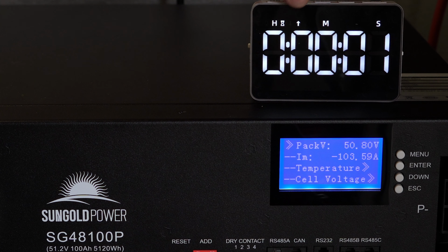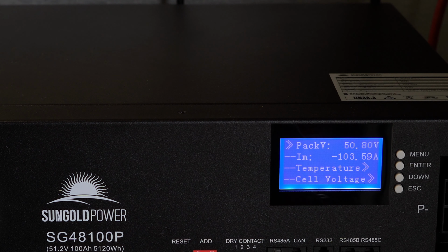All right, clearly running at just a little bit over that rated 100 amps of discharge is not a problem. So we did it for a full 20 minutes. Let me go ahead and stop it. You should see that amp value drop now.